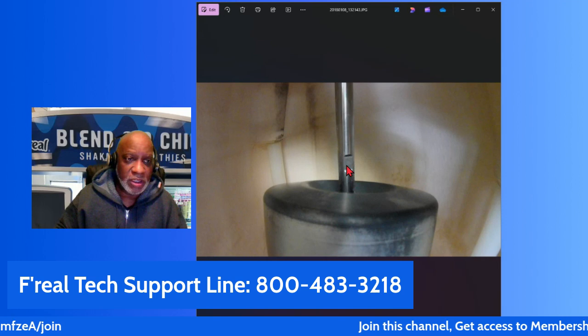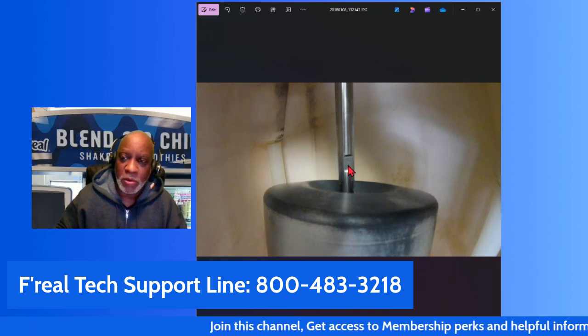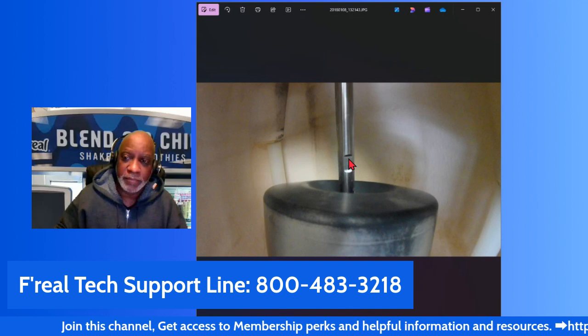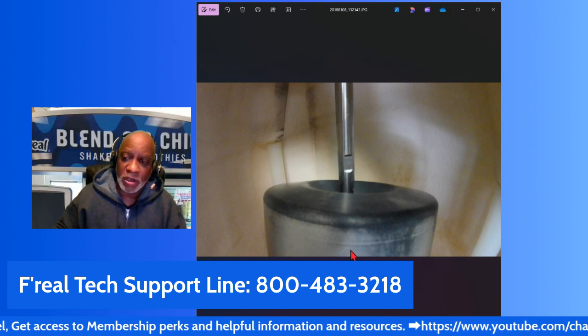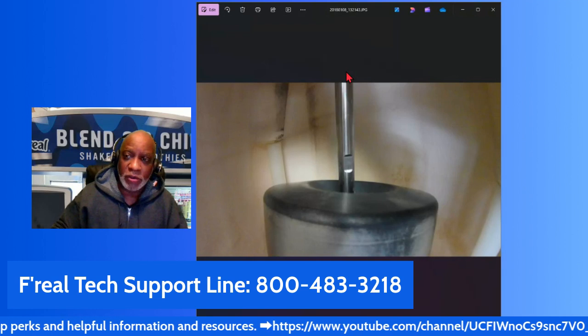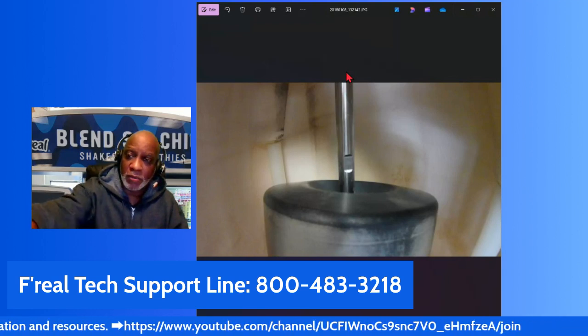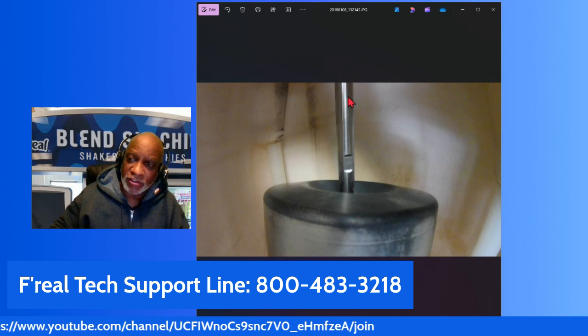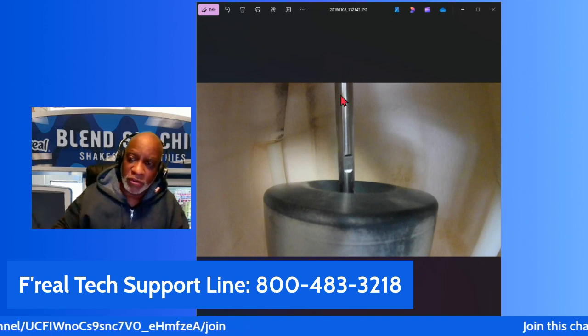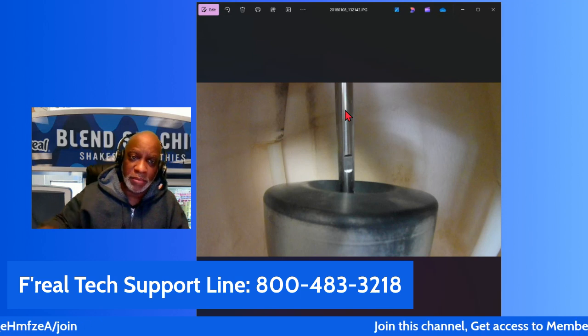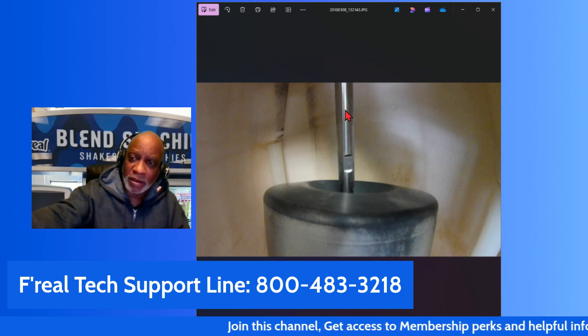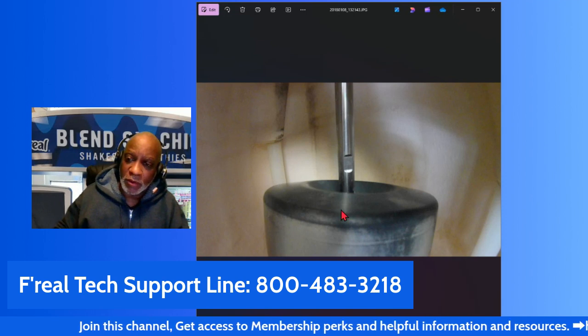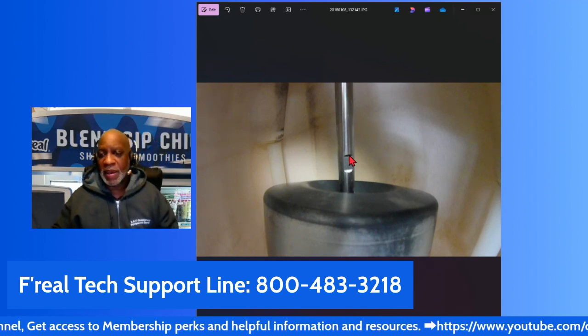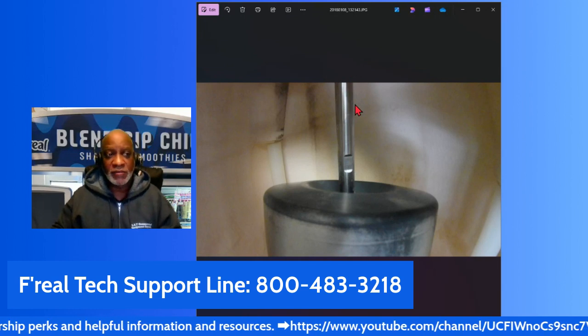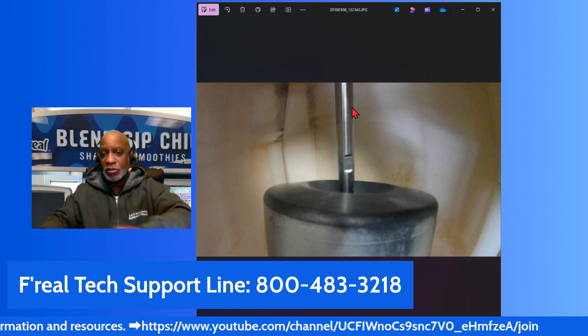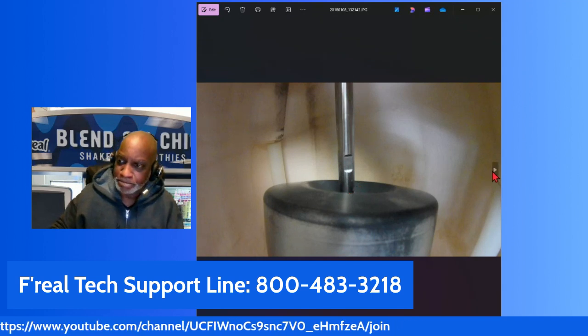And again, I'm just showing you the indentation piece here. So what you want to do is, once you get your new motor on, you're going to have to raise this cup weight, raise it up. And then what I use is a pair of pinch offs around the shaft section. And you don't have to do it too tight. You just want to use a pair of pinch offs or a pair of pliers that clamp around that shaft so that you can push this weight up past this indentation point, and then that way you have enough room to be able to tighten your mixing blade on the bottom.